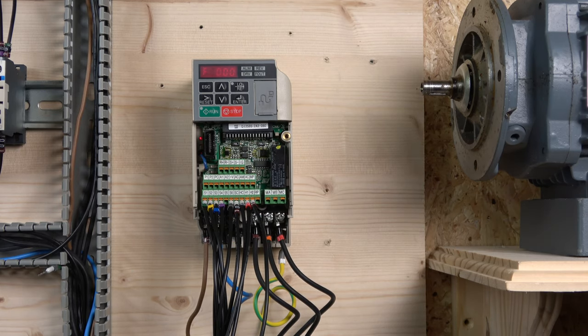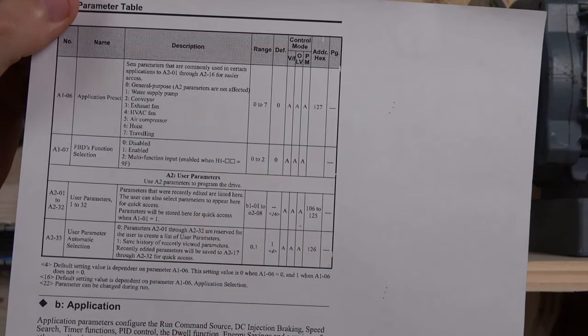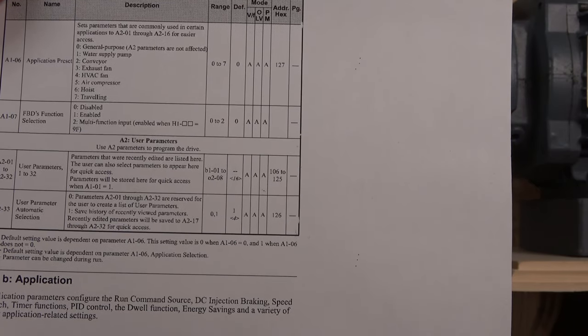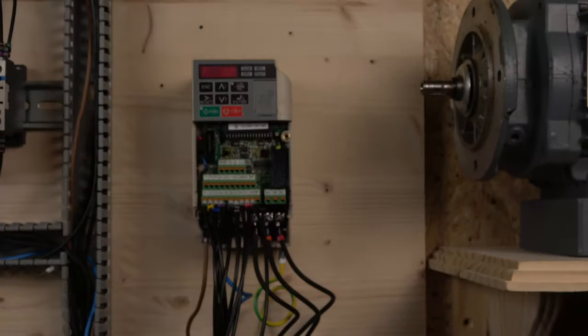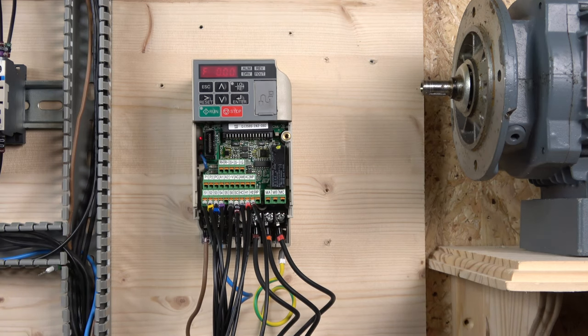Before we get into multi-frequency, I want to quickly show you something I mentioned earlier regarding presets — similar to what Siemens calls macros, but Yaskawa has been doing this for years. If you go to parameter A1-06, you can select application presets such as water pumps, conveyor, exhaust fan, and so on. Select one and it will pre-program all the relevant parameters for you, then you just follow the wiring diagram and you're good to go.